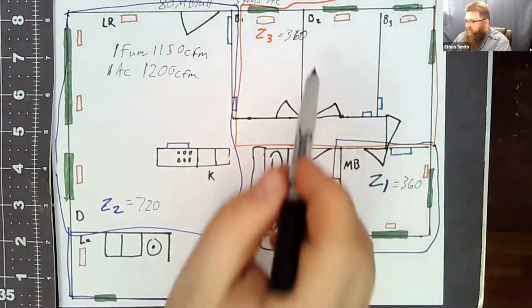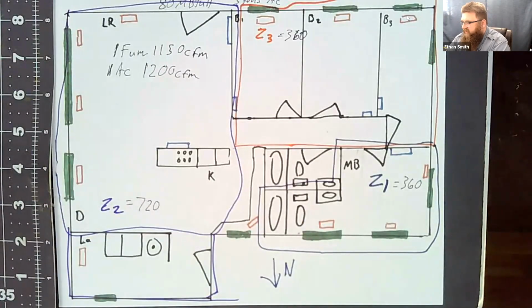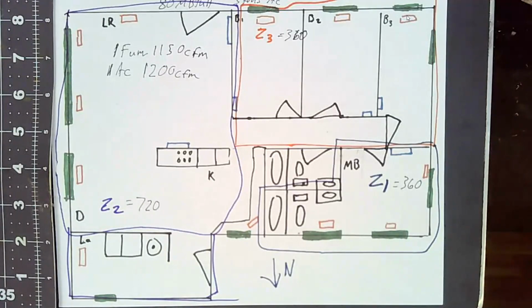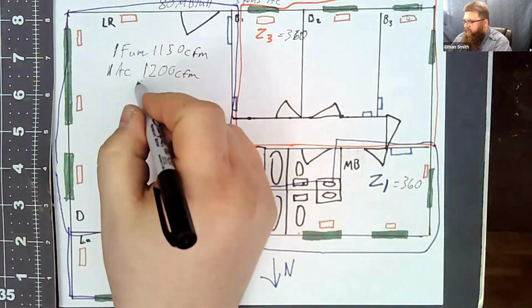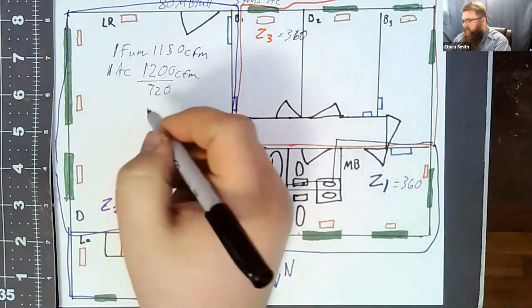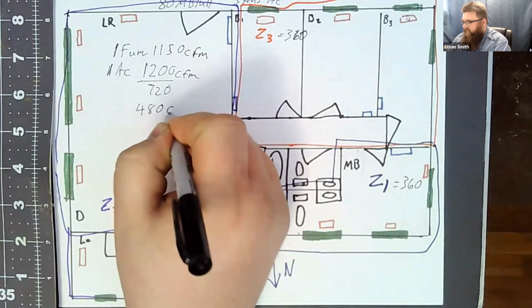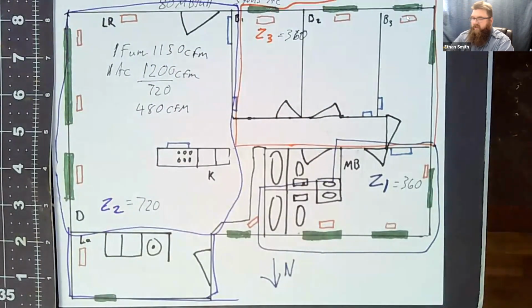But if I close zone 1 and zone 3 and just call in this living room, dining room zone, zone 2, what's my problem? Too much static. I got too much airflow. So we have an excess airflow problem. Because if we take 720 from 1200 CFM, we're left with 480 CFM. So I have to deal with that somehow.